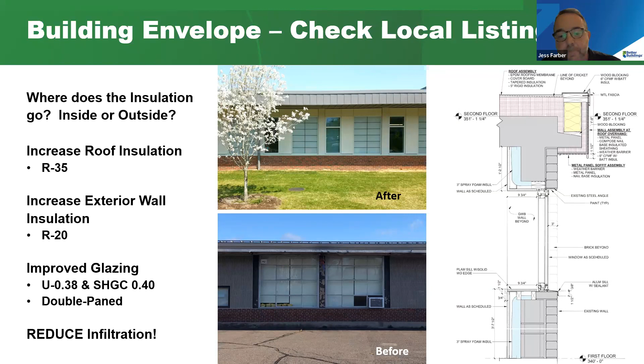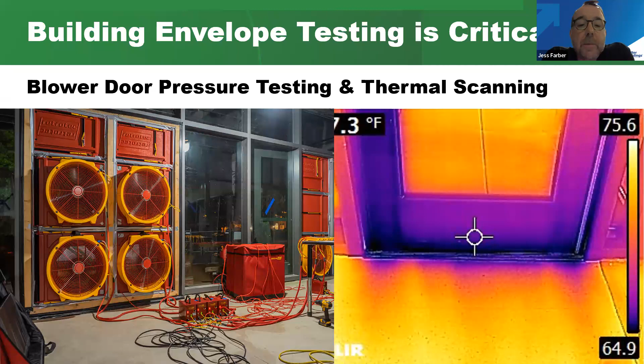One key step, if you've gone to all this trouble: in the typical commercial world, when we think about mechanical and electrical systems, we don't even question the need for commissioning those systems. The building envelope is as critical as anything when it comes to that too. A combination of blower door pressure testing and thermal scanning can help you understand how your building is performing from an envelope perspective. You can do this on an existing building to find where it could be leaking and make improvements, or during construction to make sure it was built properly to meet your goals and targets. It's a key piece to understand how the building envelope is performing.